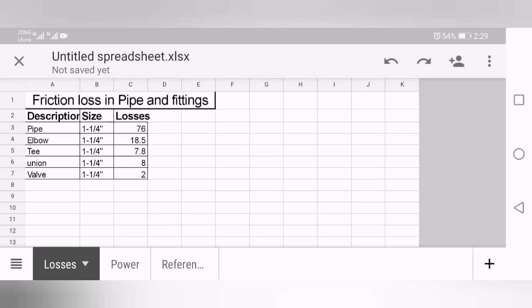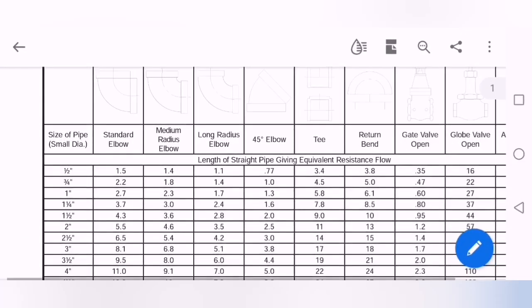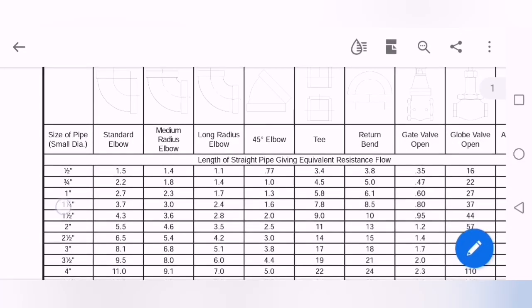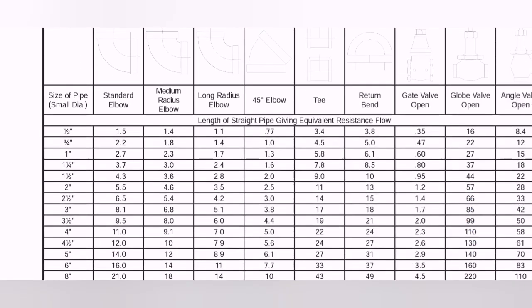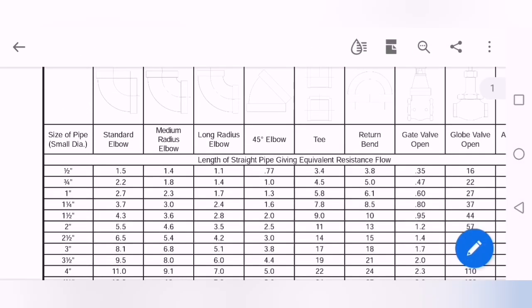From where did I calculate this? I just calculated this from this table. Like one and one-quarter has 3.7, I have five elbows, so 5 multiplied by 3.7. If you have 6 elbows, 6 multiply by 3.7, and so on.